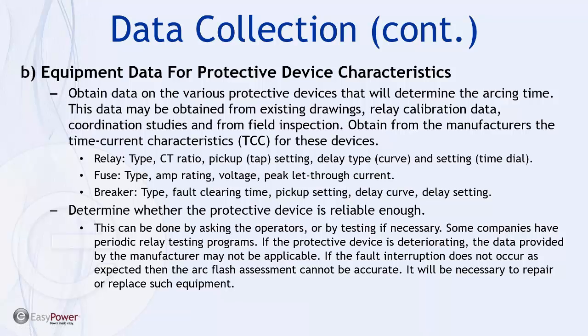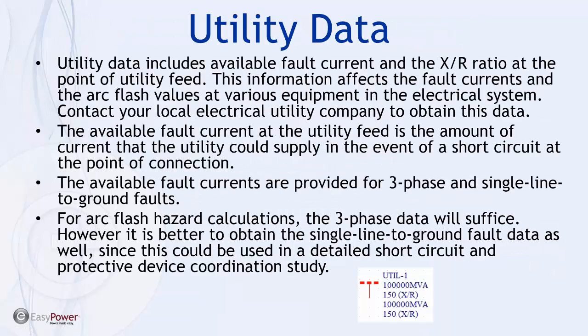It's relatively easy, if we're having multiple trips on a particular relay or breaker, to tweak the trip time a couple notches just to keep things up and running. But as an electrician on the maintenance or swing shift doing that just to keep the plant running, you may not be aware that you've drastically changed the arc flash hazard that that device is protecting workers from. The thoroughness of data collection is important.